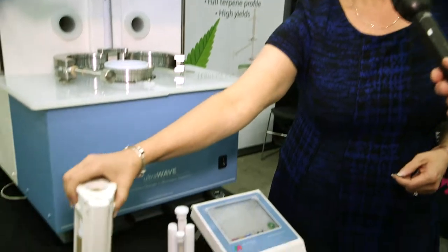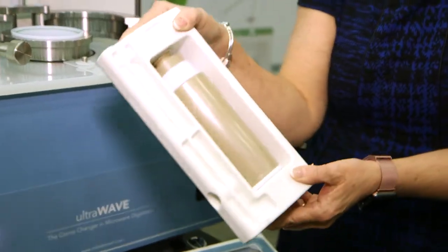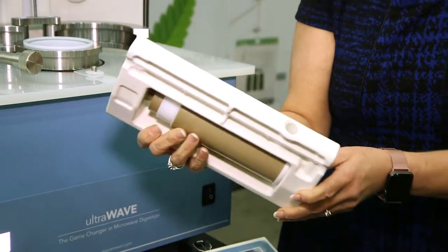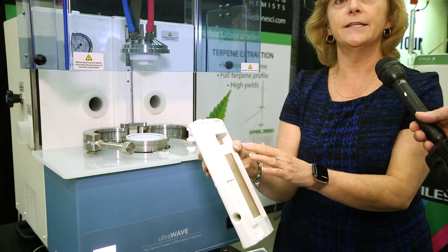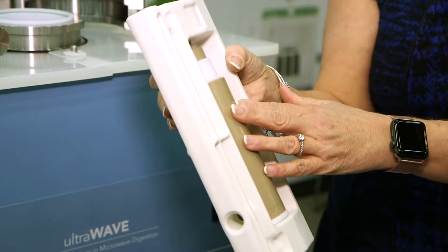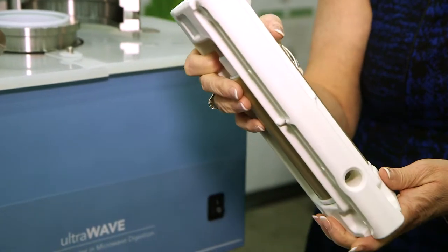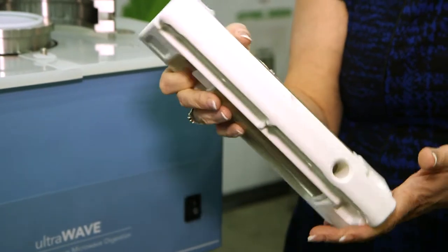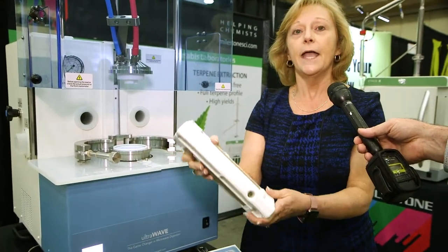There's a lot of things that differentiate it from rotor-based systems, but let's start with the digestion vials themselves. In rotor-based systems, the vessel has a lot of safety precautions built in, and the sample is placed inside a Teflon liner, along with the acids that are being used, and then these are placed into a carousel with similar sample types that go into a rotor-based microwave oven.